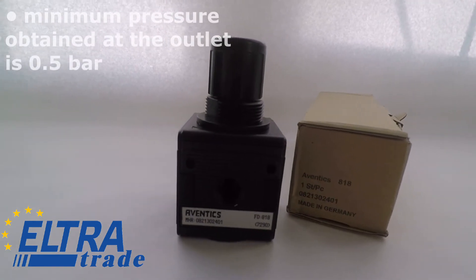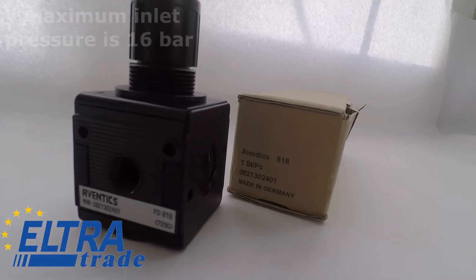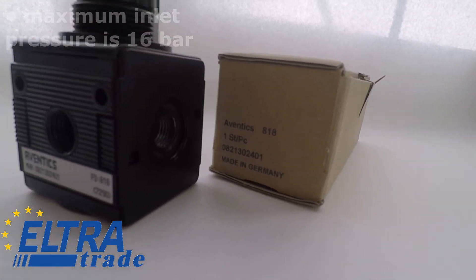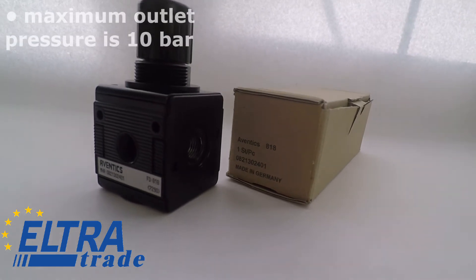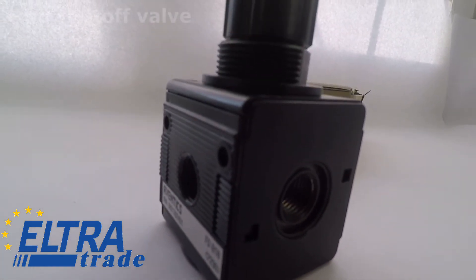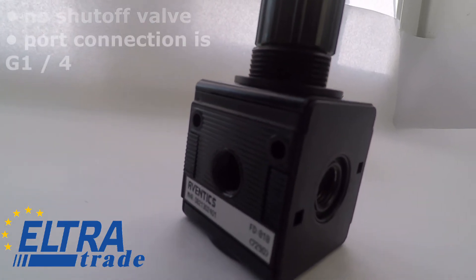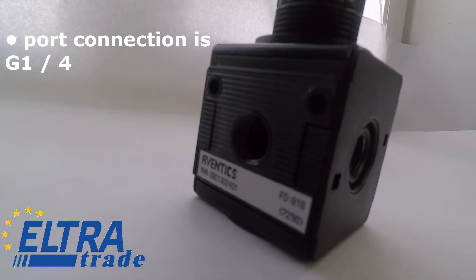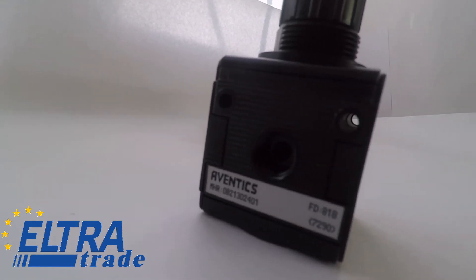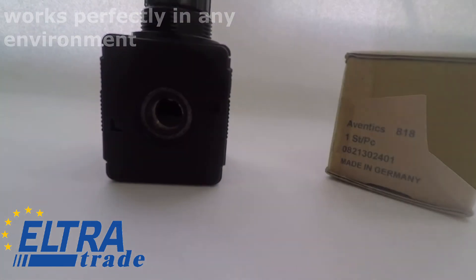Specifications: minimum pressure obtained at the outlet is 0.5 bar, maximum inlet pressure is 16 bar, maximum outlet pressure is 10 bar, no shutoff valve, port connection is G1/4. The Aventics pneumatic regulator works perfectly in any environment.